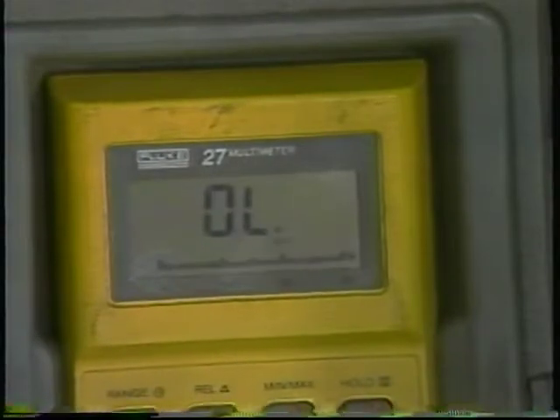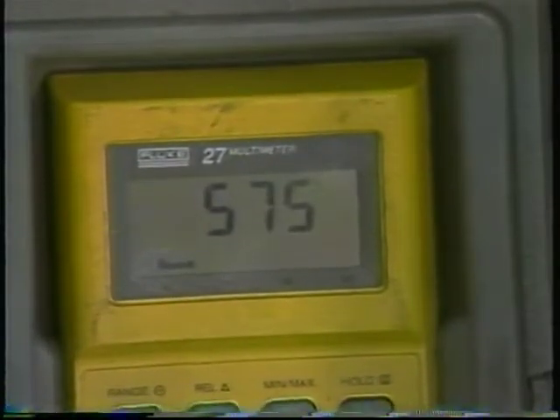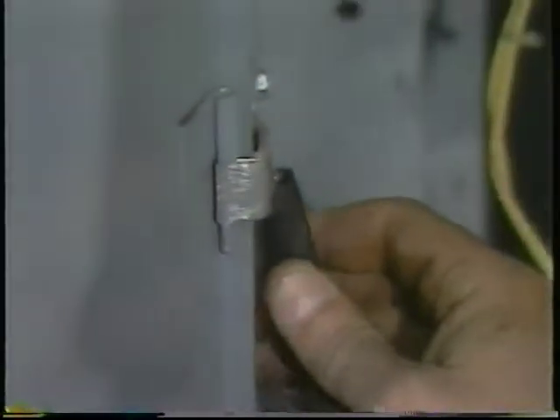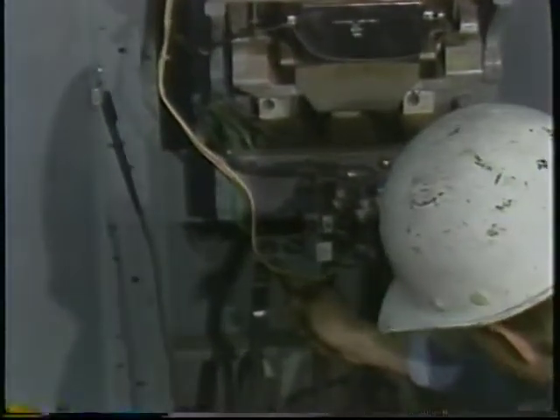With a three-phase supply, all three line-to-line voltages should be equal. Line-to-ground voltages may not be equal, however, depending on the type of three-phase supply. Be sure you know what the readings should be.